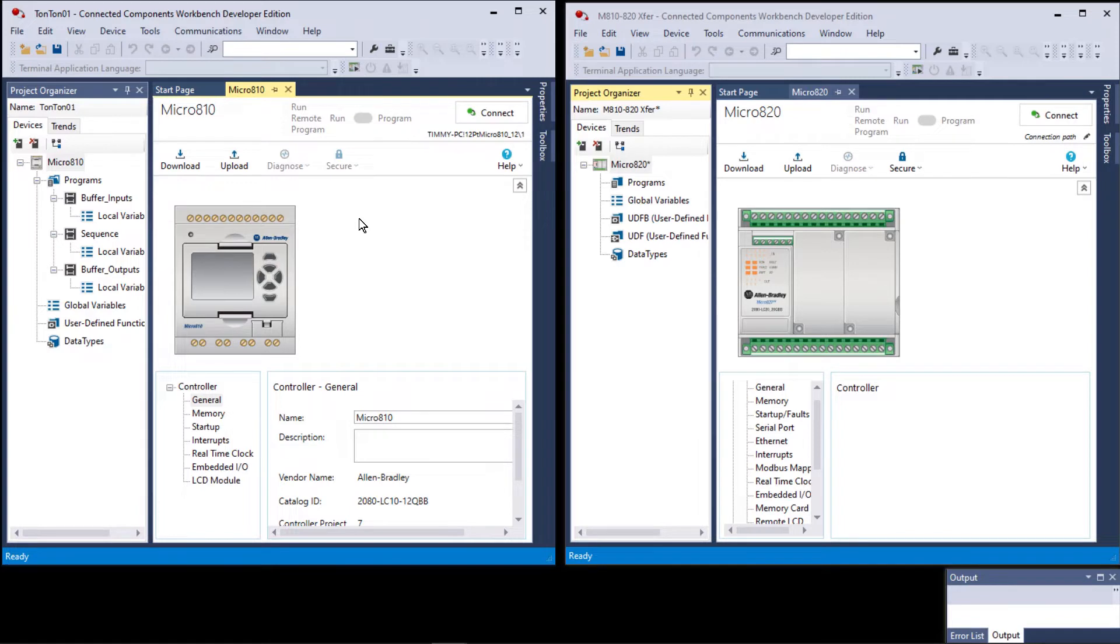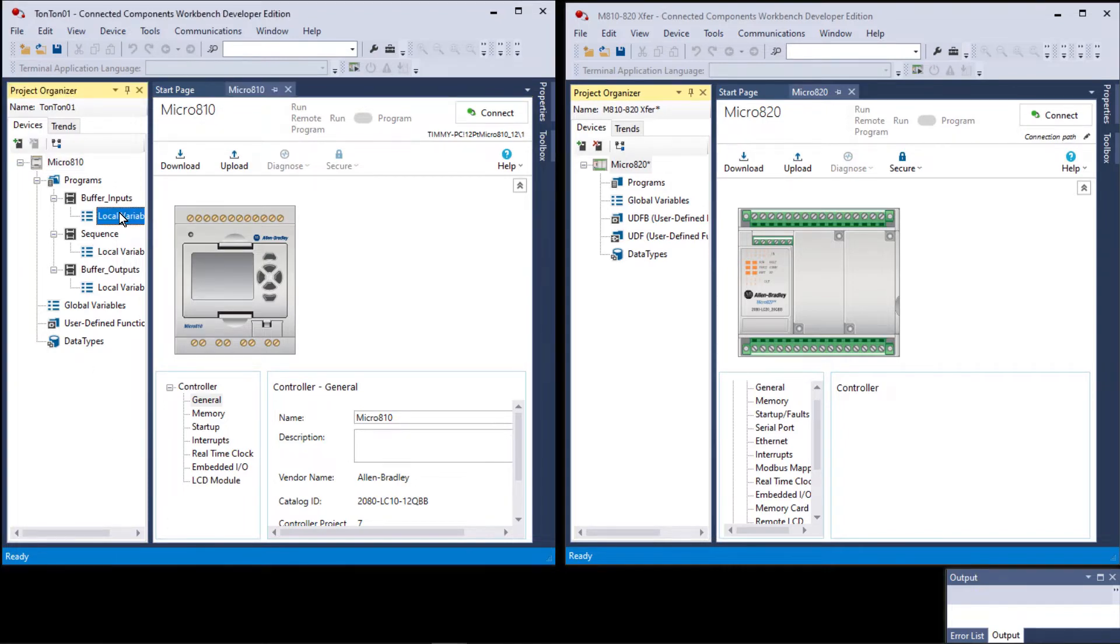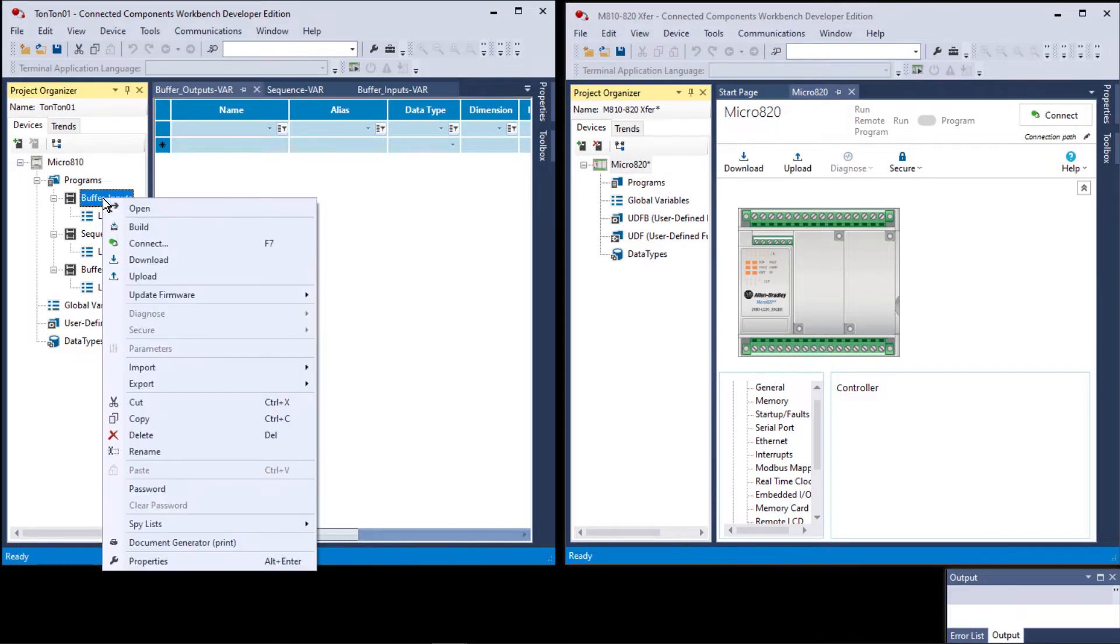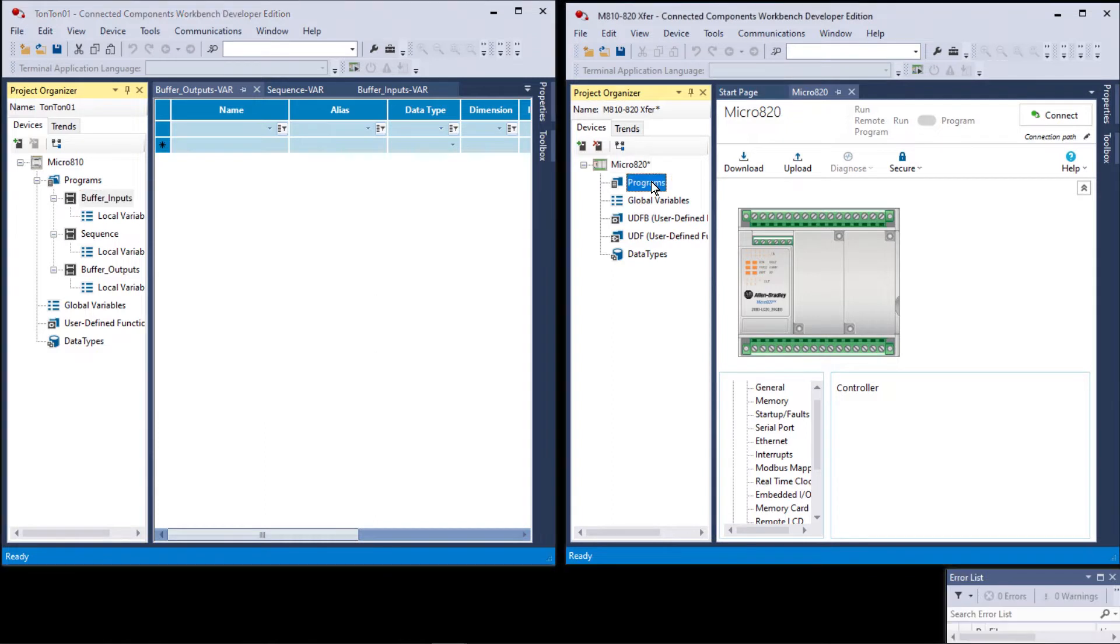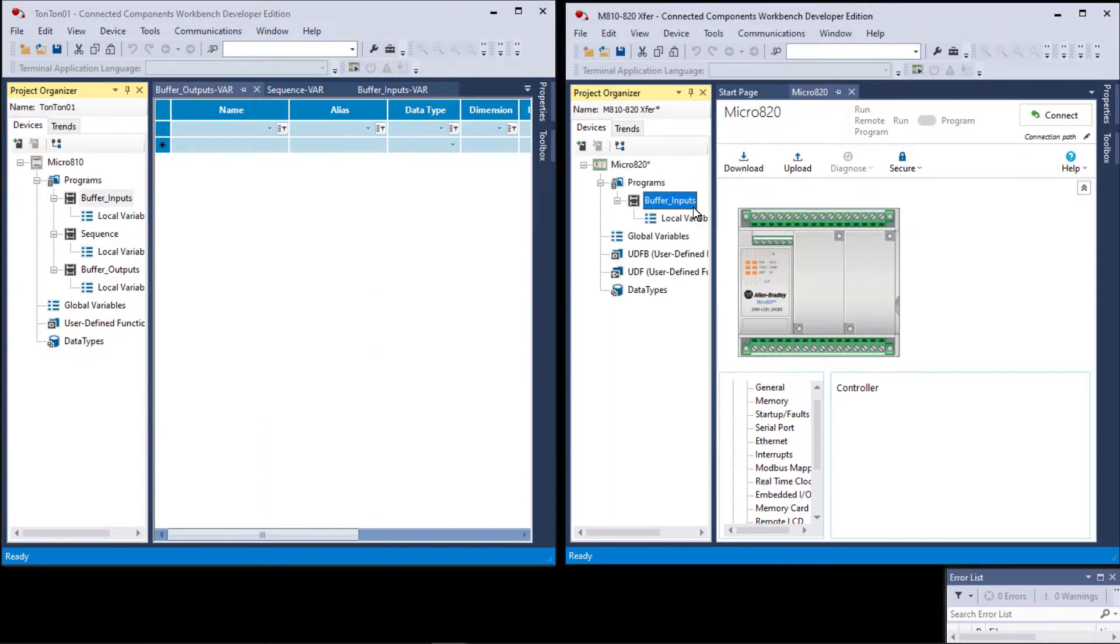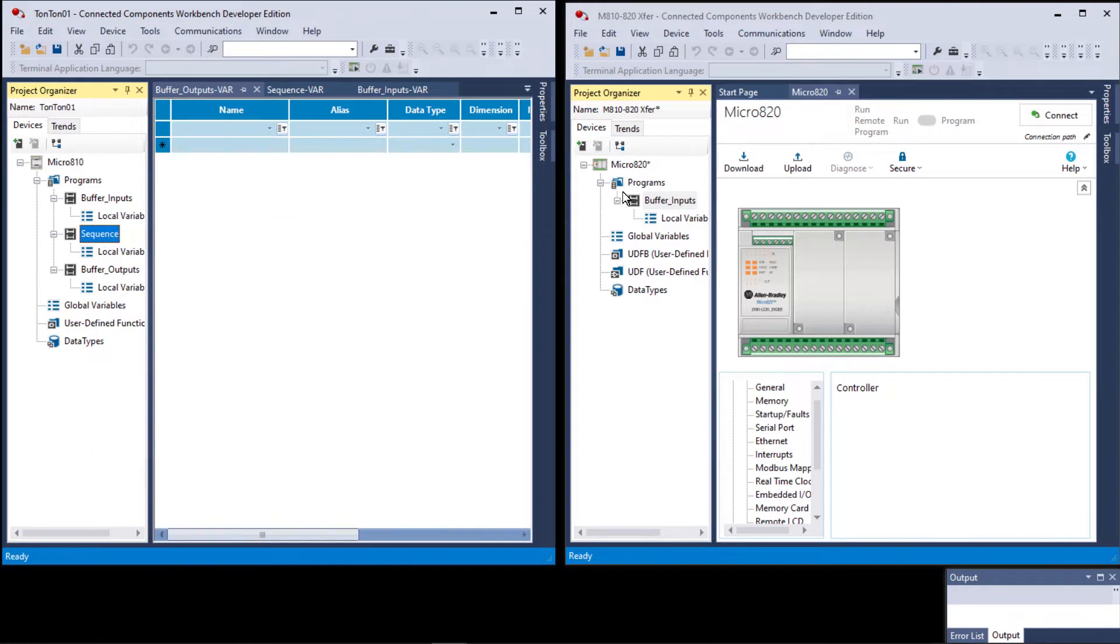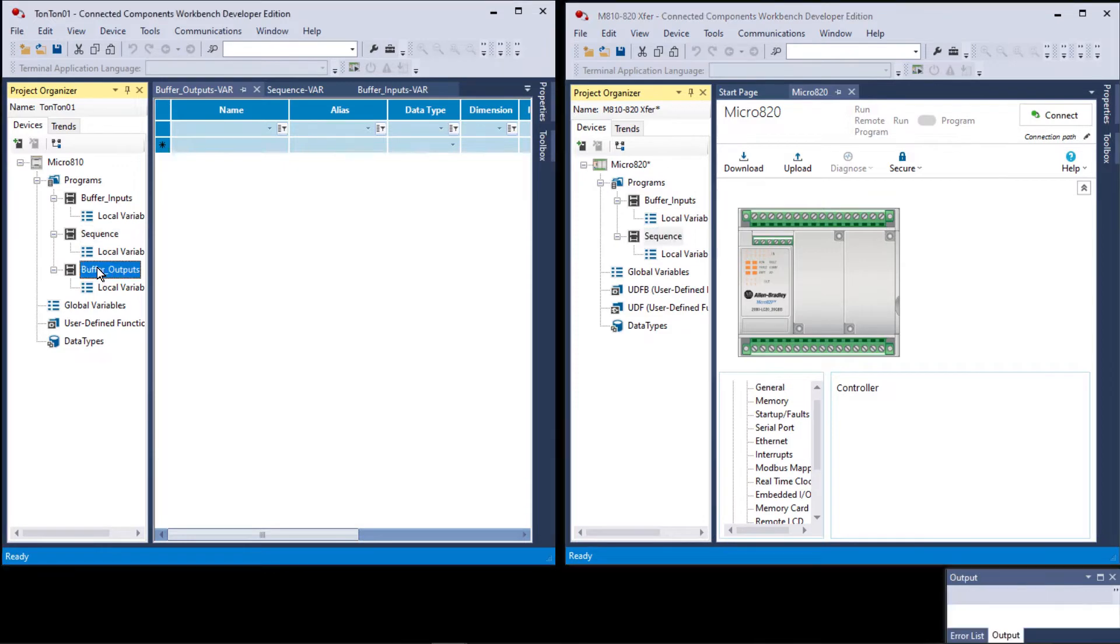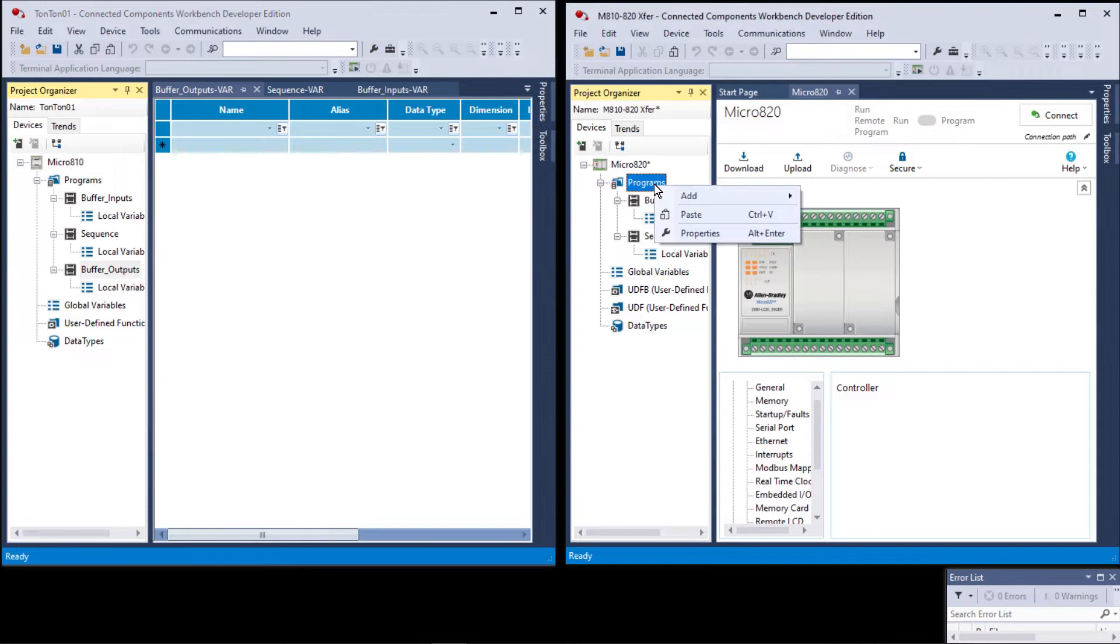In this case I'm going to use the 820. Let's begin by copying programs from one controller to the other. One thing I will share with you—copying a program does not necessarily copy the variables. Let's right click on buffer inputs, go over to our 820, right click and paste. Now let's go to sequence, right click, copy programs, right click, paste. Let's go to buffer outputs, right click copy, right click paste.